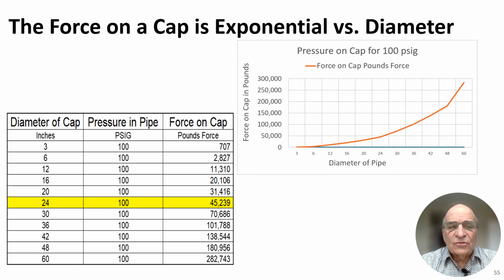As I stated, this crew had been used to installing smaller diameter mains, and the force on a cap is not linearly proportional to the diameter. It's exponentially proportional to the diameter. So let's say a gas main that was half that size. Well, that would have a relatively small amount of force on it, as you can see here, whereas a gas main that was 24-inch in diameter has a significantly larger force on it. Go even higher, and the force gets even larger. 36-inch main would be up here.